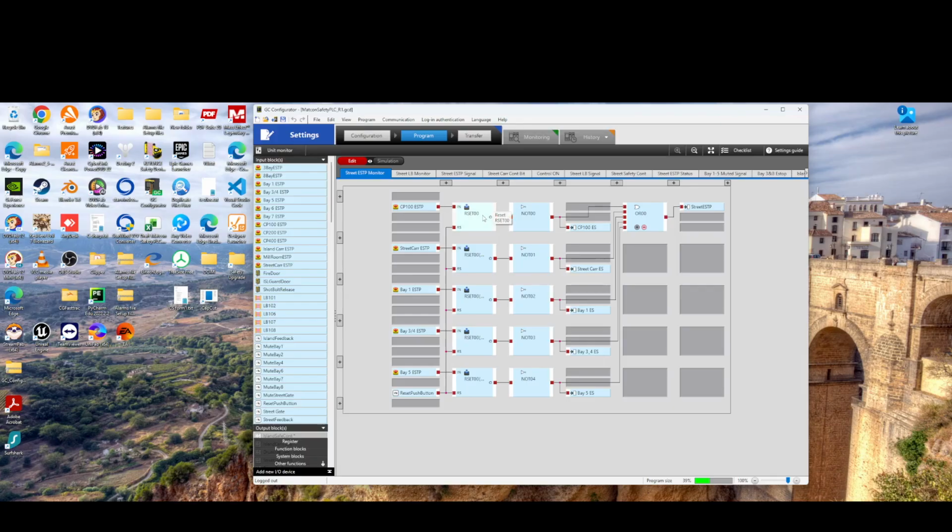What we have in the next section is the locking, quote-unquote, relay. Once this comes on, no matter what happens, if you turn off the e-stop again and pull it back out, this is not going to reset until you hit the reset push button.